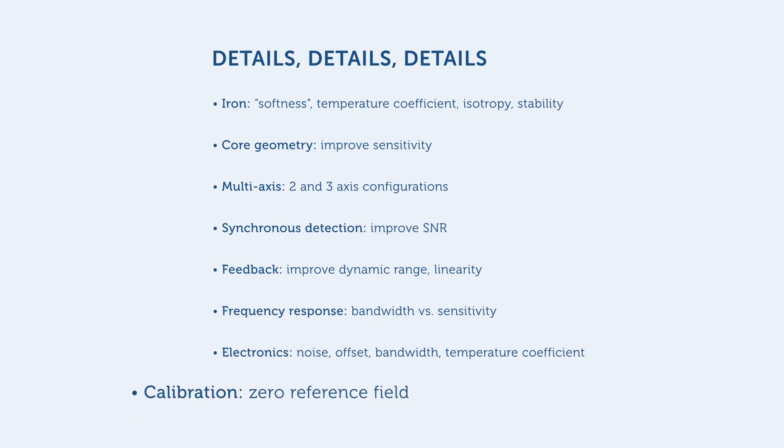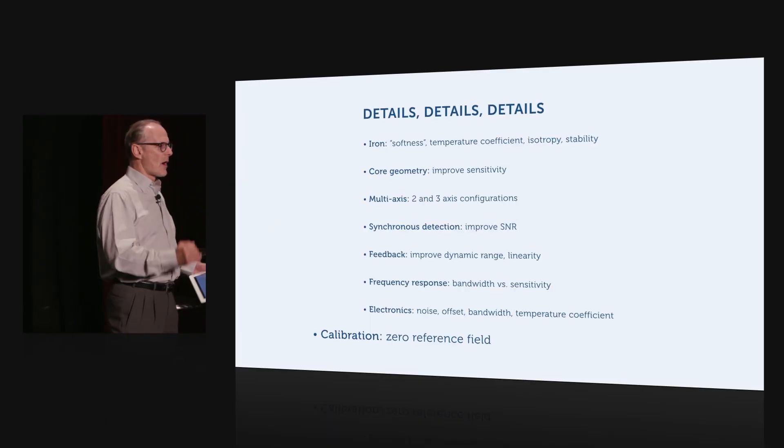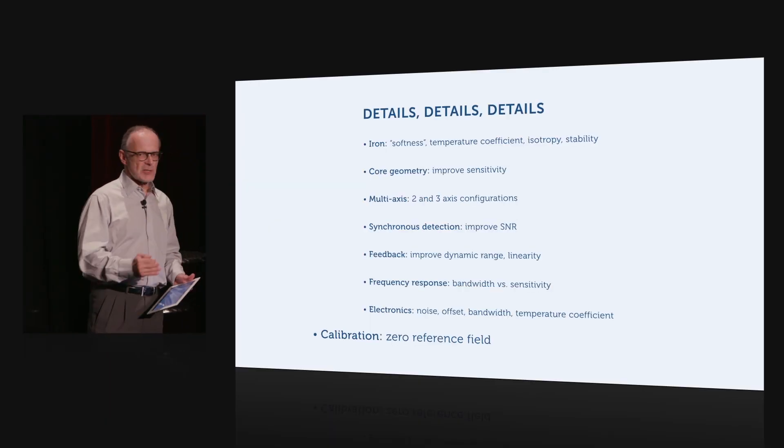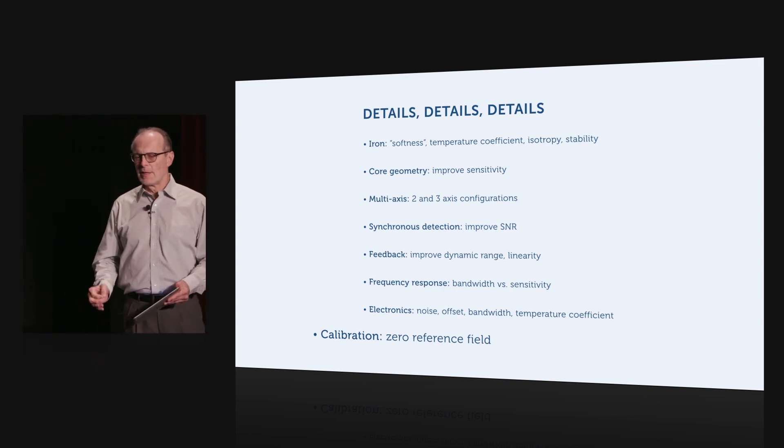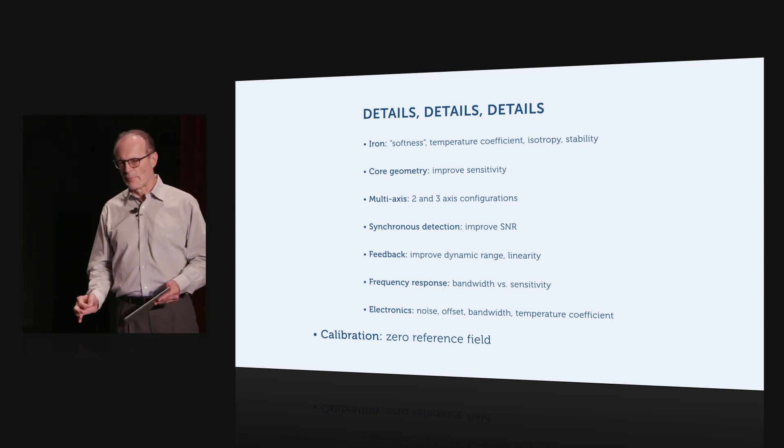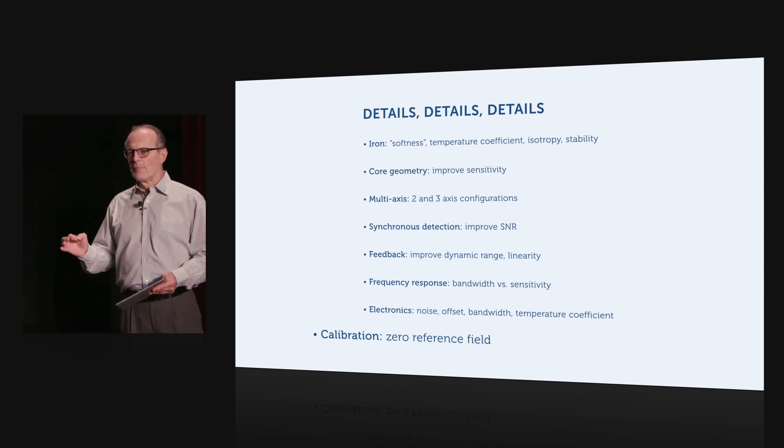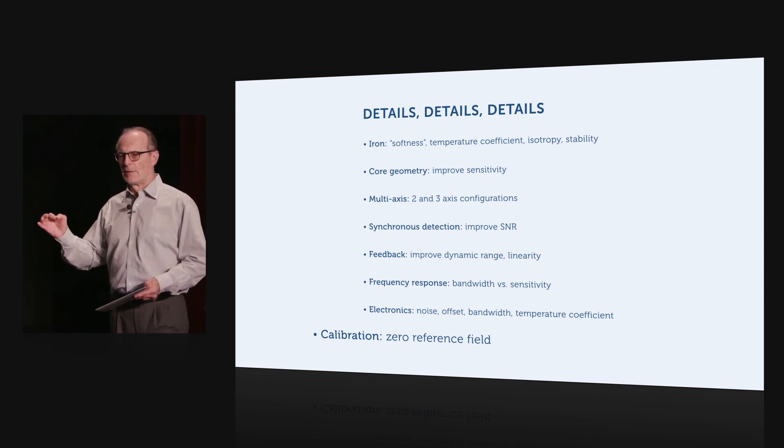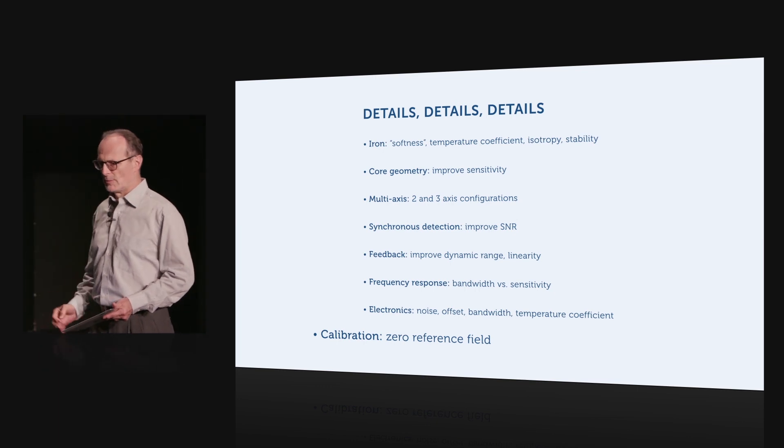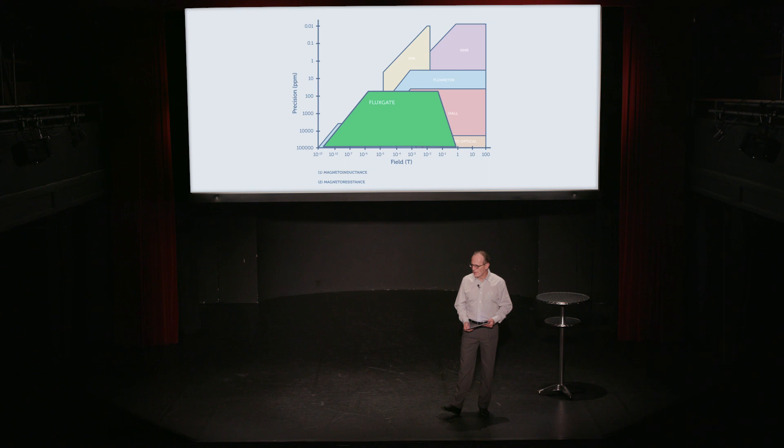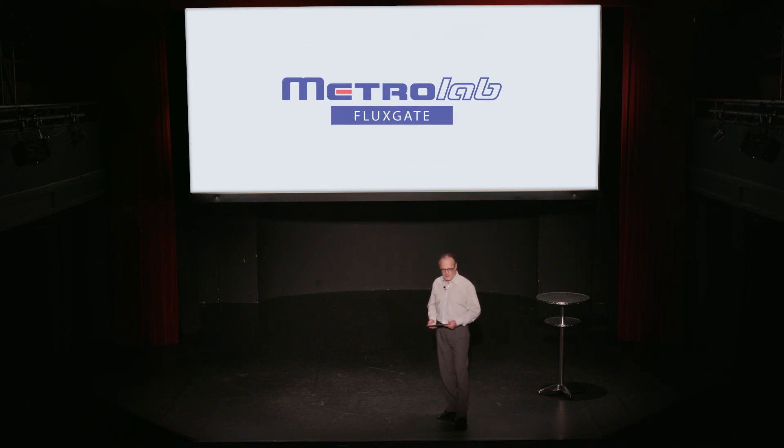Finally, as always, it's important to calibrate the instrument properly. What's especially difficult with flux gates is having a zero field reference because the flux gate is so sensitive at zero fields. Okay, now that was a very brief introduction to flux gate technology. I hope it has whetted your appetite to know some more. And I thank you for listening.